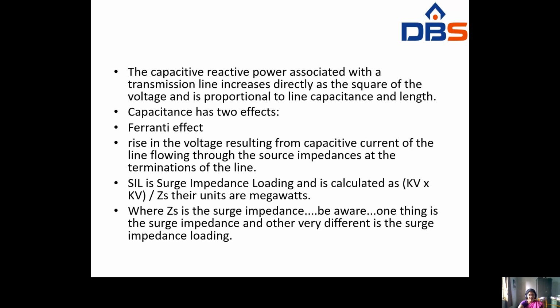See here, the capacitive reactive power associated with the transmission line increases directly as the square of the voltage and is proportional to the line capacitance and length. So whenever the voltage value increases, the capacitive reactive power also increases.